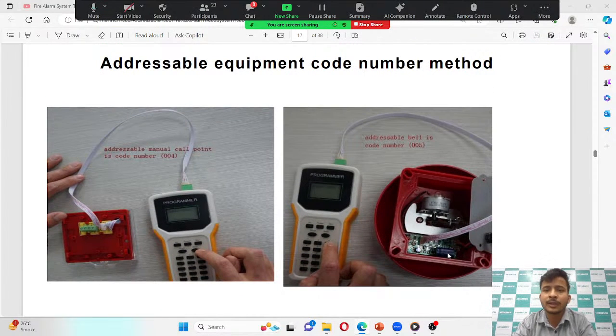Then the same procedure applies for the MCPs and for the sounder bells, sounder strobes or hooters. With that programmer you will get one ribbon cable. MCPs have one programming port. You need to connect that ribbon cable there, and same as with detectors, you first press the read button, then enter the address which you want to give the MCP or the sounder, then press the write button.